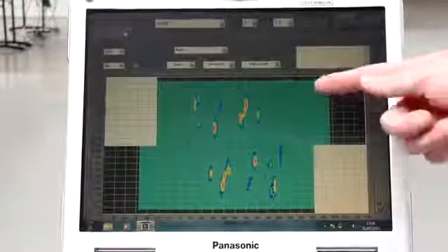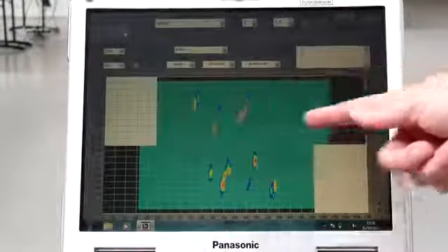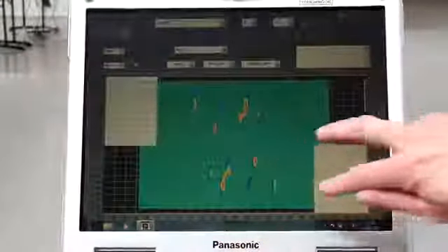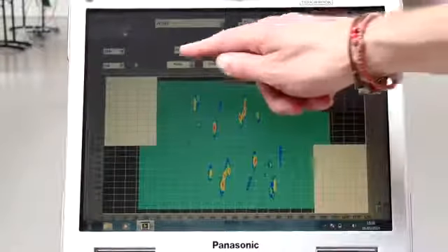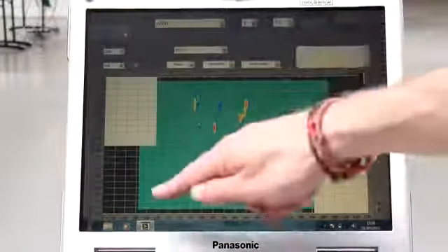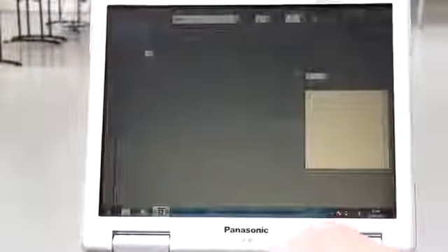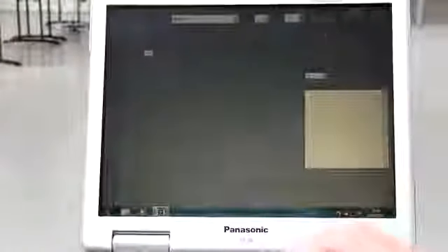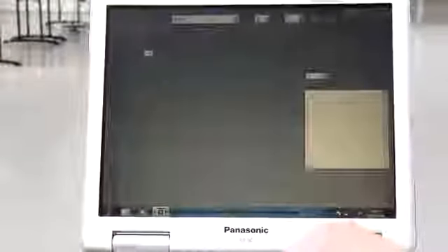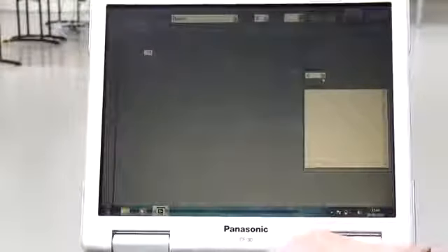The plate tab shows in detail the corrosion map of each scan pass that has been taken to map out the corrosion on the plate that is being inspected. Once in the tank screen, it will appear empty as no scan data has been collected yet. We select the diameter of the tank that we are going to inspect, either by typing a value in or using the up and down buttons as I'm showing you now.